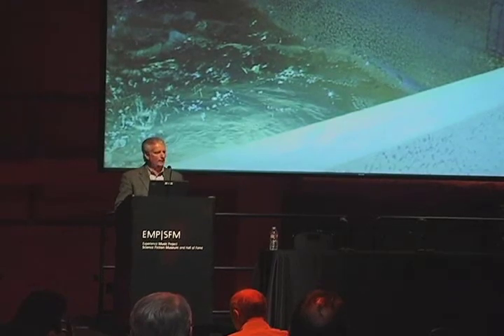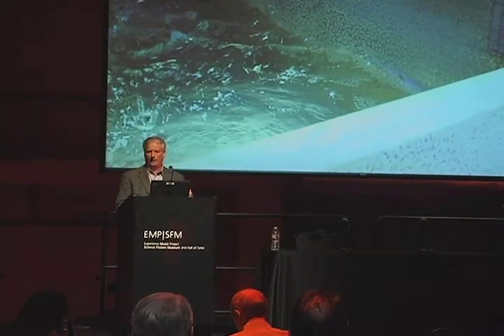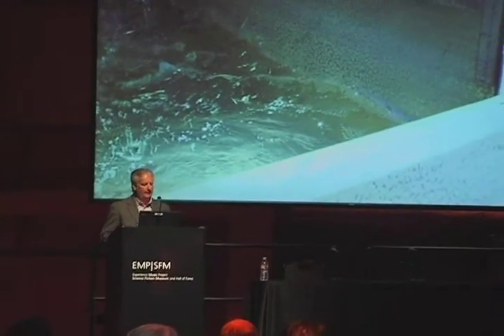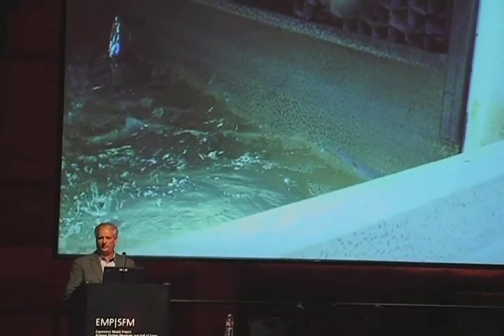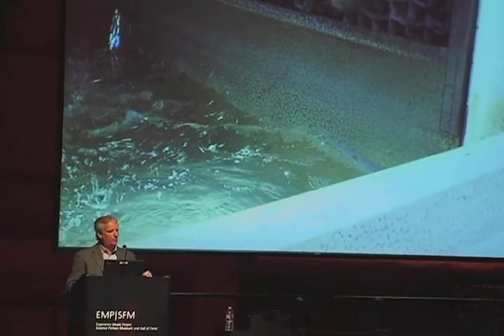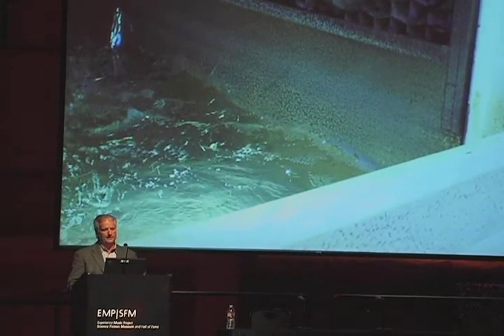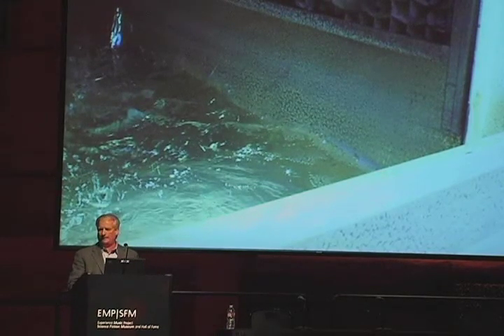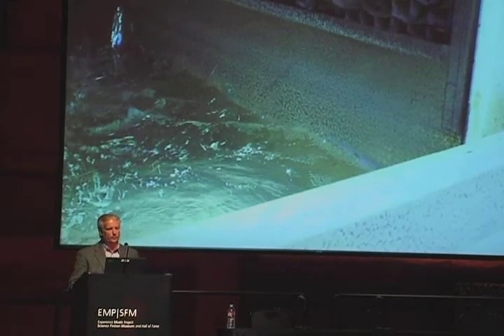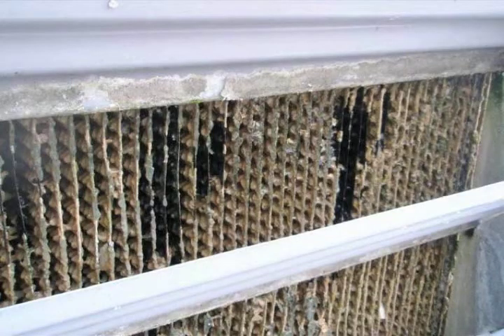And you can take these things like little dust things and remove them. But the problem is you're removing the barrier that's protecting the steel cooling tower itself. We're seeing a lot of our clients moving away from galvanized towers. Unfortunately, they're still very, very inexpensive, so we still see them coming out. So there might be changes in the water treatment program that you need to make to help protect that, especially in the first 90 days. These towers need to go through a process of passivation and pH control to passivate that zinc barrier before you start the water treatment program. If you don't do that, you're going to see pretty rapid deterioration of these towers, so they won't last very long.